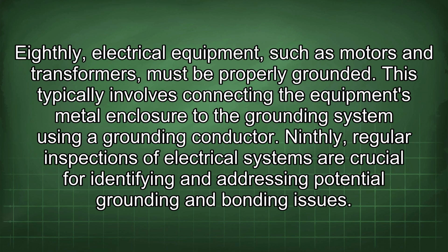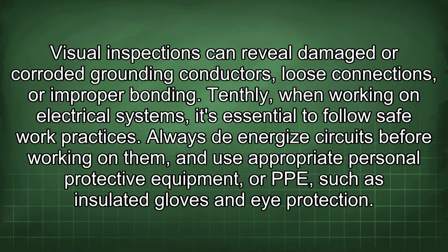Non-metallic conduits require the installation of a separate equipment grounding conductor. Eighthly, electrical equipment, such as motors and transformers, must be properly grounded. This typically involves connecting the equipment's metal enclosure to the grounding system using a grounding conductor. Ninthly, regular inspections of electrical systems are crucial for identifying and addressing potential grounding and bonding issues. Visual inspections can reveal damaged or corroded grounding conductors, loose connections, or improper bonding.